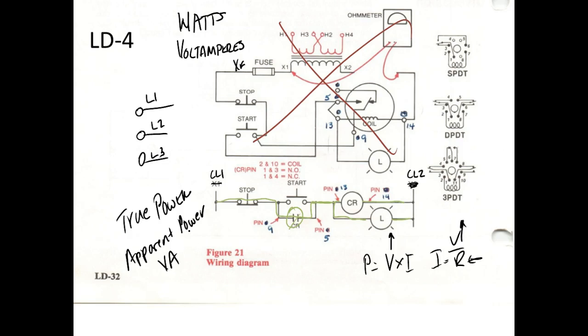Transformers have to be able to produce apparent power, because the sources are going to have to produce apparent power. So that's why transformers are rated in VA. The small ones are rated in volts and amps. You'll never see them rated in watts, but they'll have the number of volts and the number of amps. Your big transformers are going to be rated probably in kVA, because they have to provide apparent power, right?